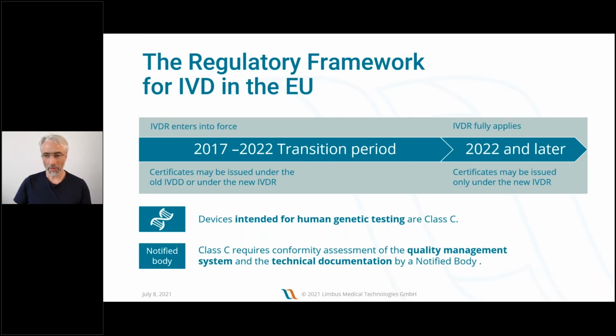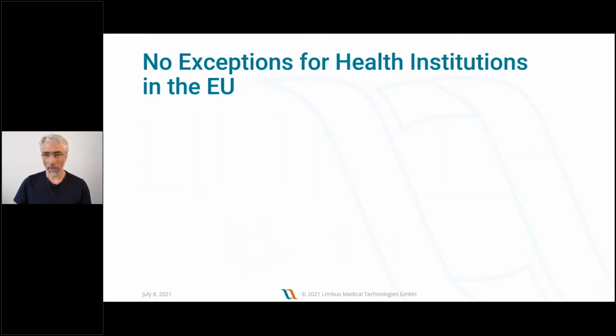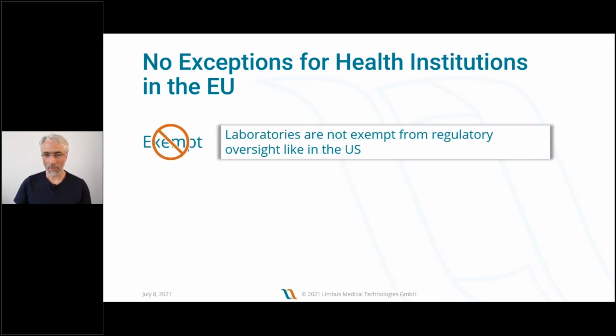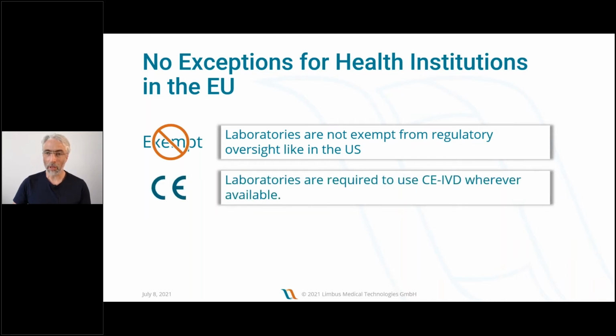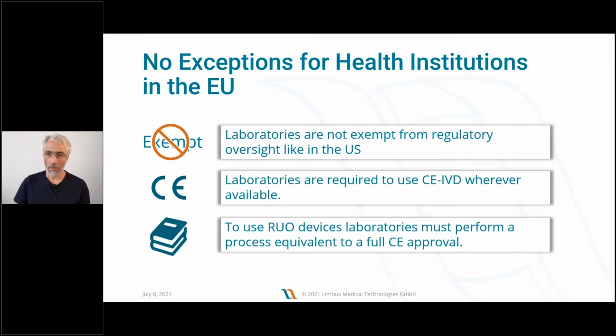The regulation in Europe is also slightly different if you compare this to other markets like the United States. While in the United States, laboratories are exempt from regulation, they are explicitly not exempt from regulation in Europe. Laboratories in Europe are required to use CE-IVD products wherever possible. And if laboratories want to deviate from that and want to use research use only devices in their processes, they must perform a process that's almost equivalent to a full CE approval. And I'd like to explain in a little more detail what that means for laboratories.